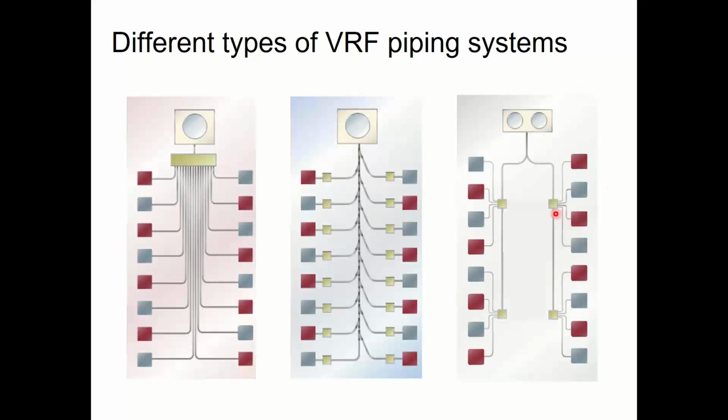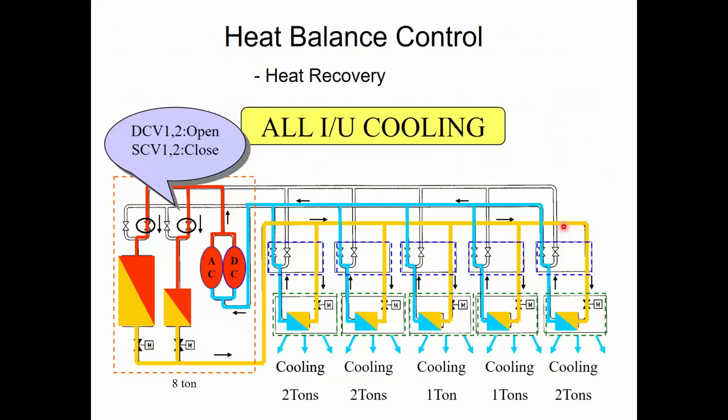There's also a third scenario, which is kind of a hybrid of those two. So in this case, everybody didn't get their own little converter box to go from 3 to 2 pipes. I've grouped them. So these 4 guys on the right have 1 converter box, and 3 pipes come in and 2 pipes go out. But that means all 4 of these guys have to choose heating or cooling as a group. So this group can choose something different than the bottom group, but internal to the group, they can't get something different. All right, let's look how this works.